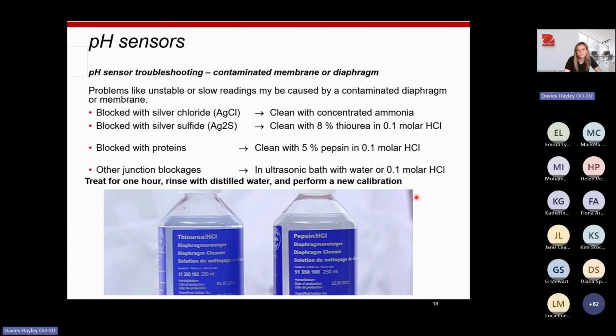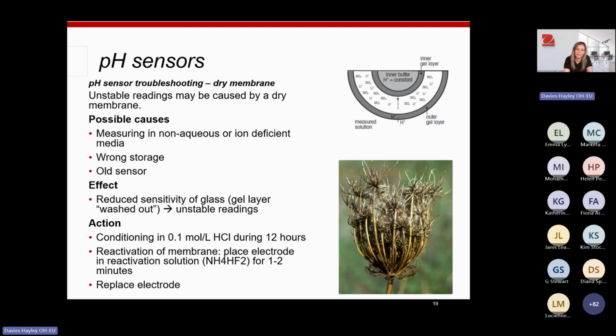With these solutions, it's recommended that you treat them for 1 hour, so you can leave them immersed in the cleaning solutions for 1 hour, take them out, rinse them with distilled water, and then, because you've maintained that, you need to perform a brand new calibration. Hopefully that would get your probes working again.